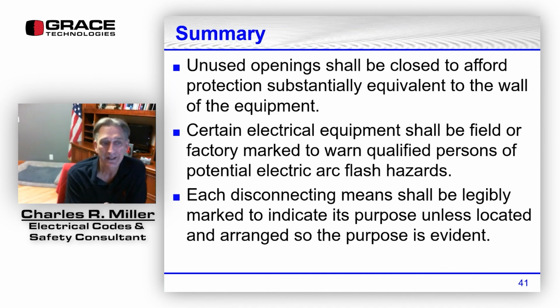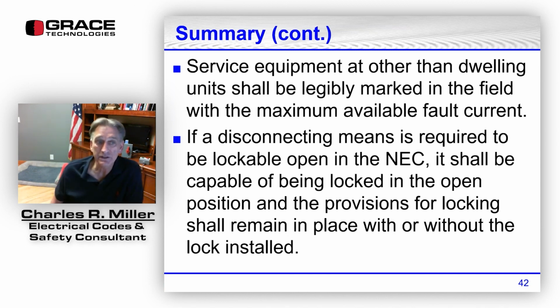Well, then they changed it to it had to be field or factory marked to warn qualified persons of potential electric arc flash hazards. Each disconnecting means should be legibly marked to indicate its purpose unless located and arranged so that the purpose of the disconnect is evident. Service equipment at other than dwelling units shall be legibly marked in the field with the maximum available fault current. If a disconnecting means is required to be lockable open, or off in the National Electrical Code, it has to be capable of being locked in the open position, and the provisions for locking or the device for locking has to remain in place with or without the lock installed.